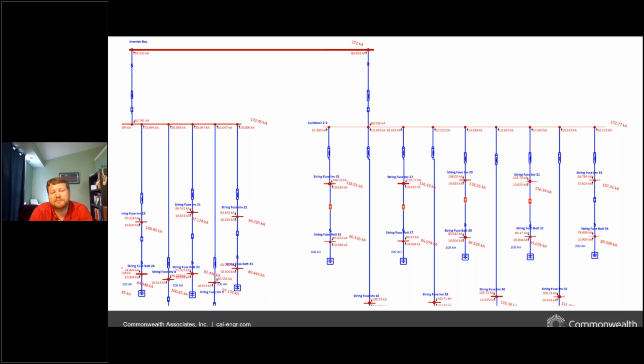Also, at the inverter bus, you have some beefier equipment, some thicker and more fault-capable handling fuses. But when we get down to the string fuses, which are on top of the battery stacks themselves, this equipment isn't quite so built. So what we find is we have challenges in trying to make sure that the equipment is rated to handle these very, very high fault currents. So as a rule, we're seeing on the DC side, generally 50,000 amps is the typical equipment maximum for handling fault currents. And what we can see here is we have fault currents at the battery that are high, upwards of around just under 100,000 amps. And we see that the actual containers that these fuses live in will have to see fault currents of around 120,000 amps.